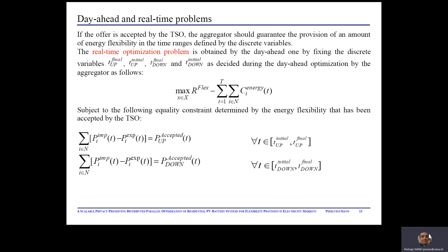If the offer is then accepted by the transmission system operator, the aggregator should guarantee the provision of an amount of energy flexibility in the time ranges defined by the discrete variables. The real-time optimization problem is thus obtained from the day-ahead one by fixing the discrete variables as decided during the day-ahead optimization by the aggregator. The optimization problem is subject to the constraints determined by the energy flexibility that has been accepted by the transmission system operator, as shown here. The real-time optimization can be carried out every 15 minutes to update the control signals for the batteries to adapt to changes in photovoltaic production and electrical loads of each prosumer, considering that the proposed parallel optimization is very fast.